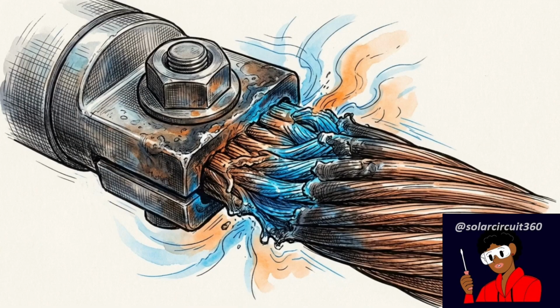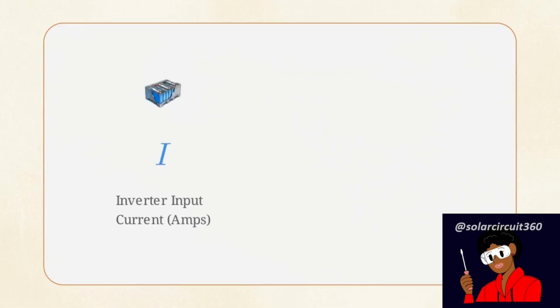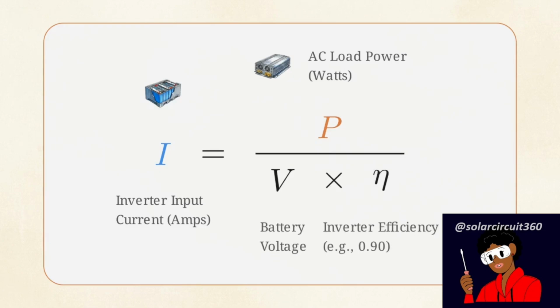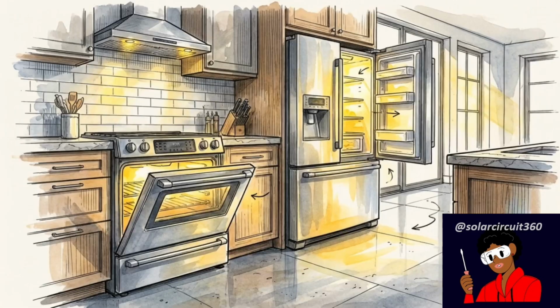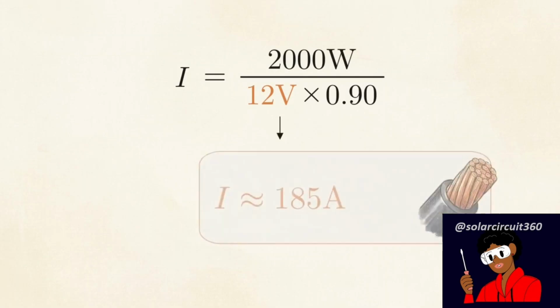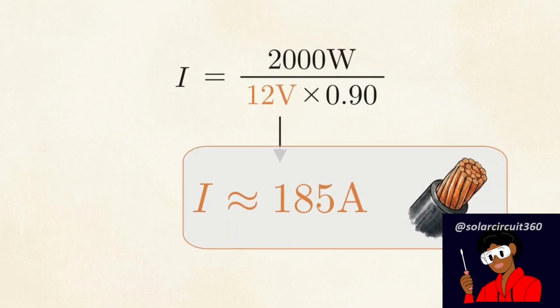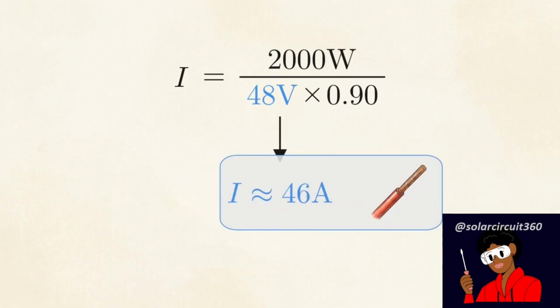Even with the voltage limits perfectly programmed, massive invisible current demands can create physical stress that software cannot fix. This equation calculates the actual current drawn from the battery. Inverter input current equals the alternating current power load divided by the battery voltage multiplied by the inverter's efficiency. Let's apply a constant load of 2,000 watts, simulating heavy household appliances. If we run that 2,000 watt load on a 12-volt system, the battery has to push an enormous amount of current. Step the system up to 48 volts, and the required current drops by a factor of 4.